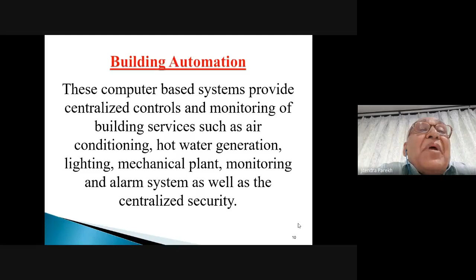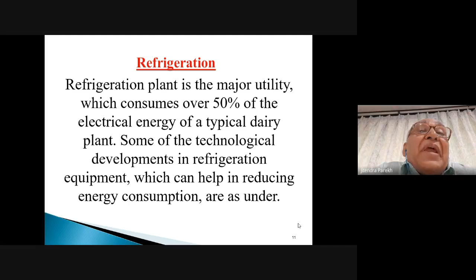Now we are talking about refrigeration, which consumes over 50% of the electrical energy of a typical dairy plant. Some of the technical developments in refrigeration equipment which can help reduce energy consumption are as under. Next, please. Here I am talking about screw compressors, which are very important in our refrigeration plant, as compared to reciprocating compressors. They give a high coefficient of performance, COP, and lesser power consumption, with other advantages like step-less capacity control to ensure accurate temperature and pressure control, thereby saving energy.